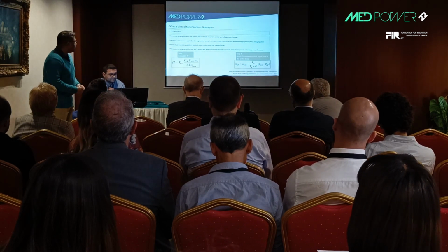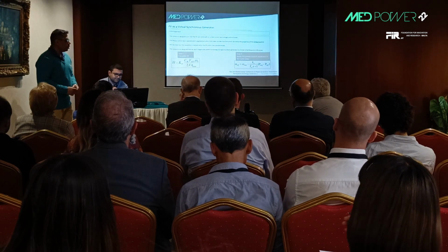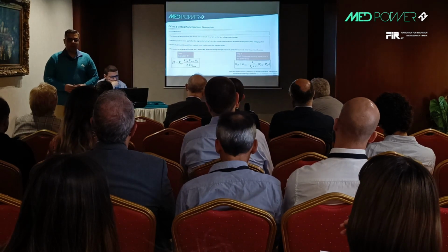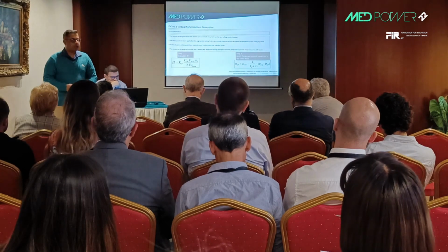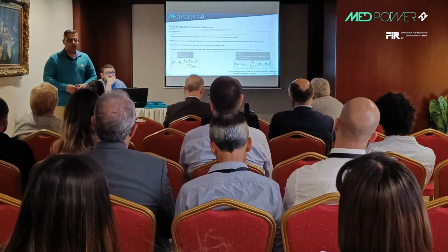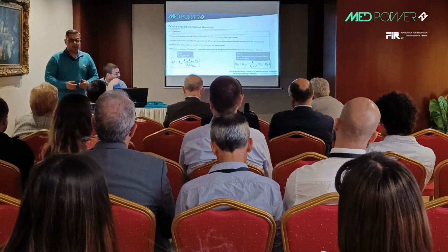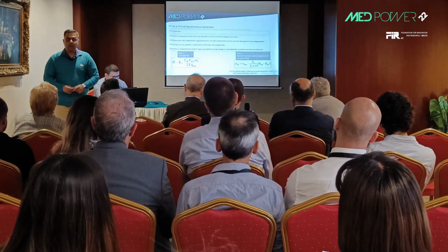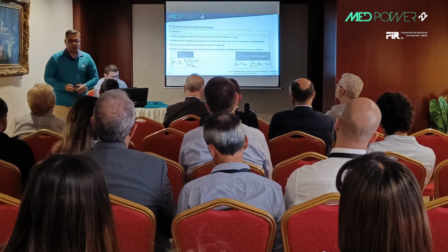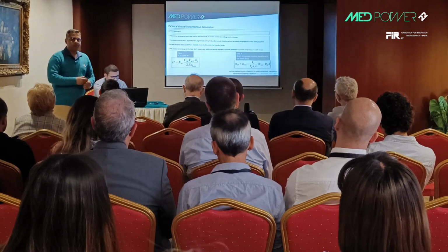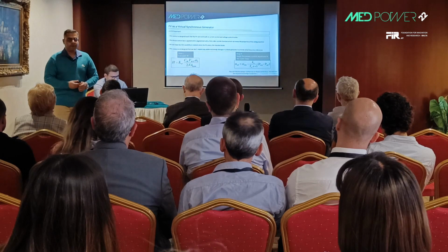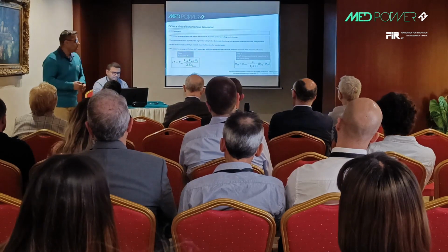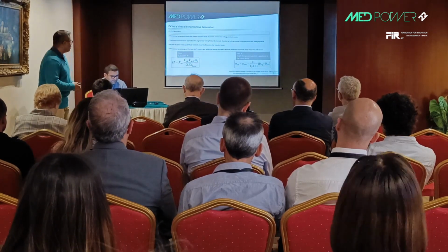Now, to have a PV as a virtual synchronous generator, the general control methodology is a cascaded controller. We have an inner current controller which takes care of the current protection and the harmonics, then an outer AC voltage controller which is responsible for controlling the AC voltage, and then another outer controller, the power controller, which gives the frequency signals, because in case of PV as a VSG, it is no more a frequency follower. It will be able to generate its own frequency, although it's a synthetic inertia device. It does not offer real mass into the system.